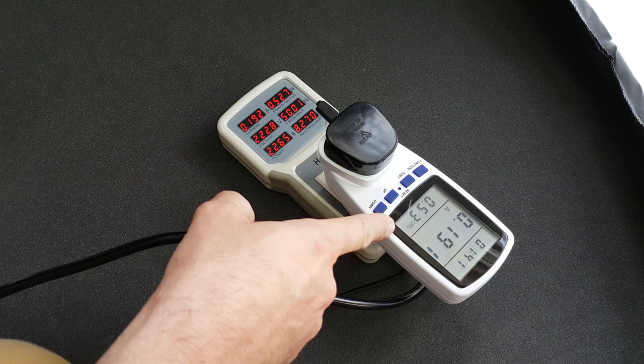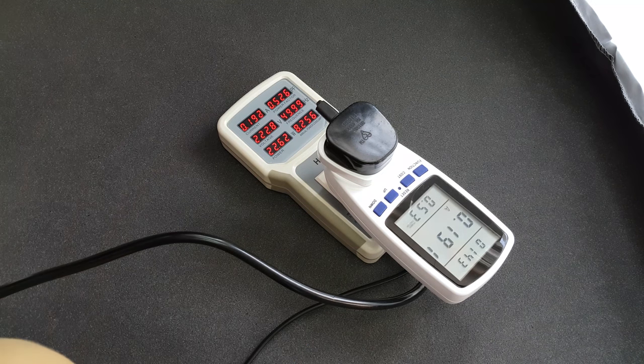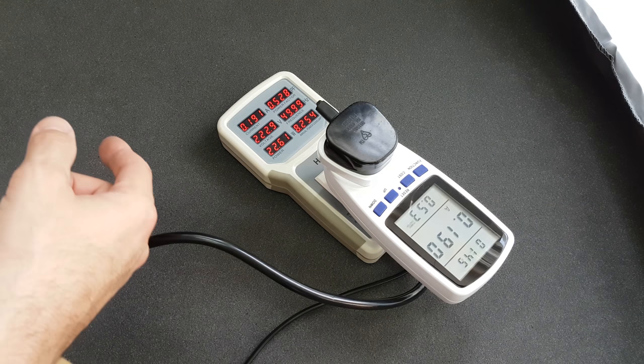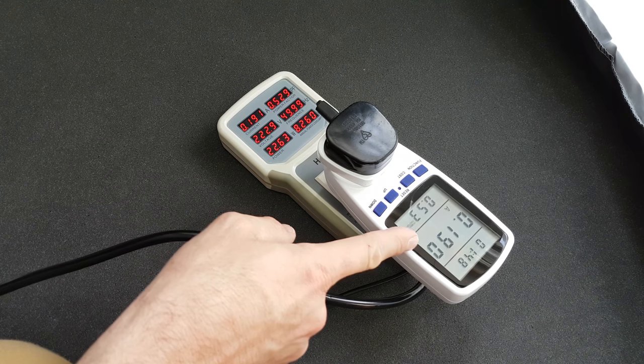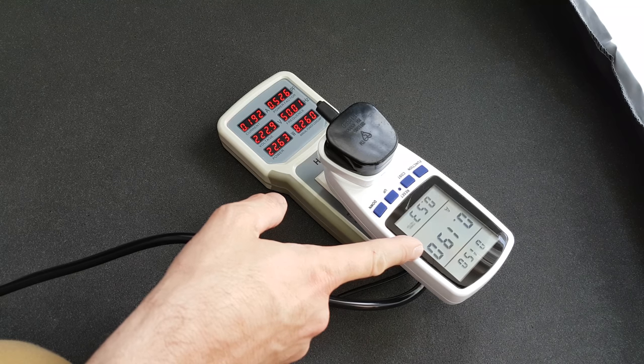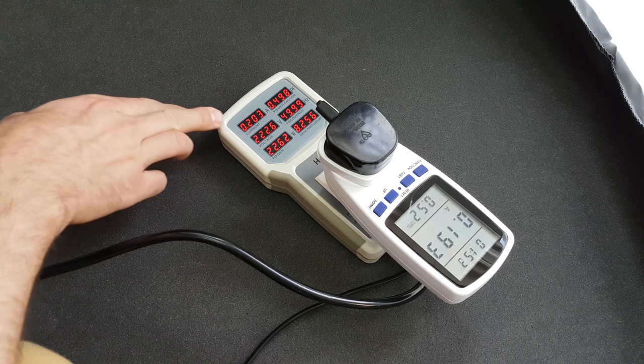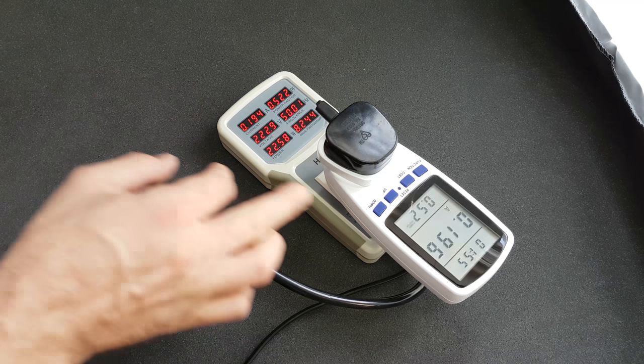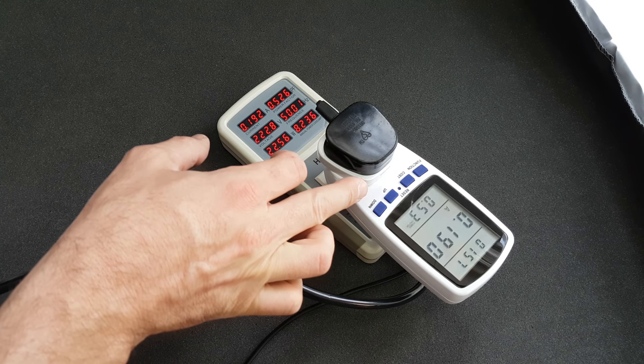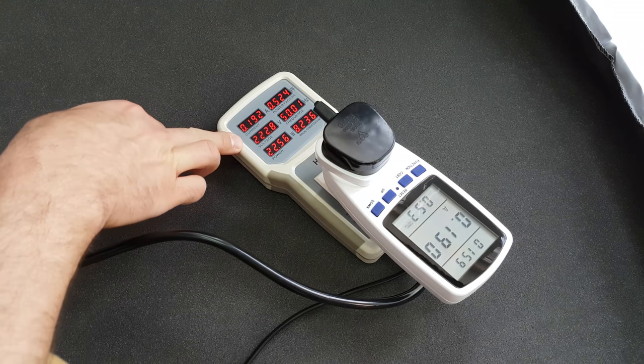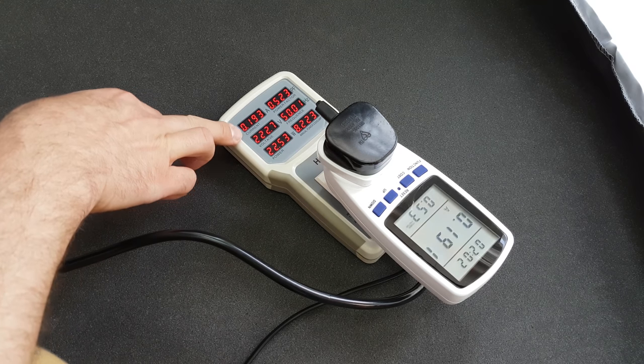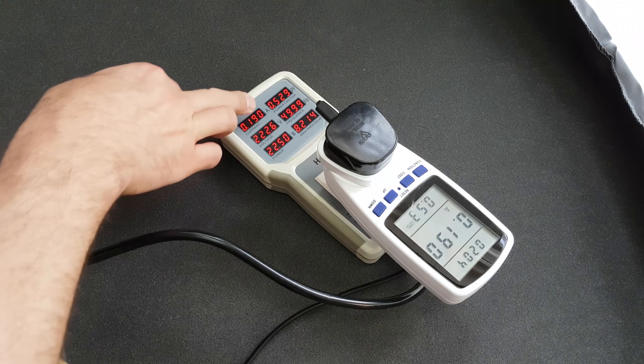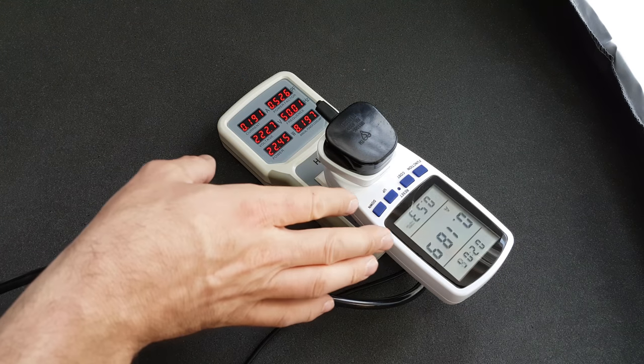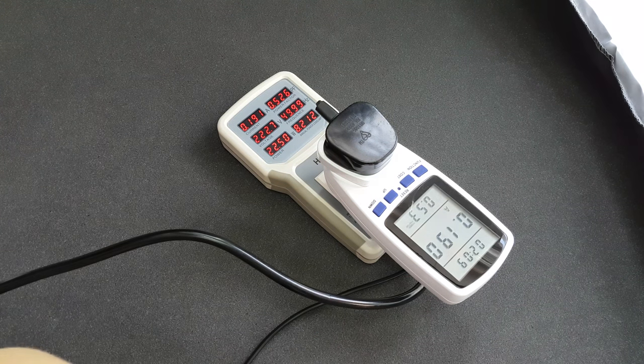We've got the power factor down here, 0.53. We've got 0.526 there, 528. And the amps are 0.190 here, 0.198. So it seems to be a little bit more here. Maybe there's a little bit of current draw from this unit additionally to here. So 0.191. 0.19, okay. There seems to be maybe a little less, but very little difference between them that could be expected.